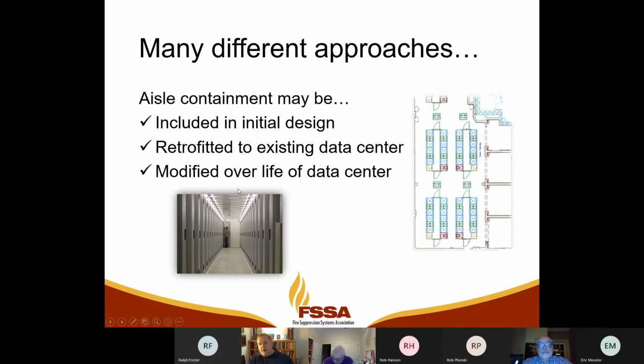It's going to do a little bit here, a little bit there. We've got a couple racks that seem to be getting too hot, so we'll hang some strip curtains here and start to see if I can address some of the bypass and make it better. Those are some of the things that happen in existing data centers to affect the fire protection.